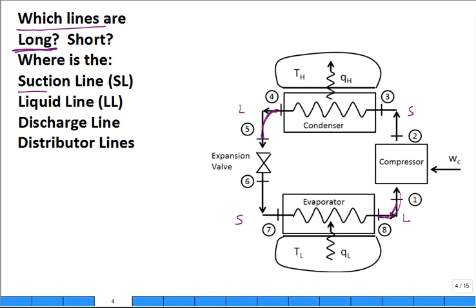Where is the suction line? The suction line. And it's going to be the long line. And so how do they get the terms? Well, the compressor is really drawing the refrigerant from the evaporator. So it's what they call sucking or suction. Pulling it out of the evaporator. When that, if you turn the system off and it went to equilibrium, the pressure everywhere would be the same. But then when you kick the compressor in, it starts to build this pressure and draw this pressure down. So it starts sucking on the suction line.